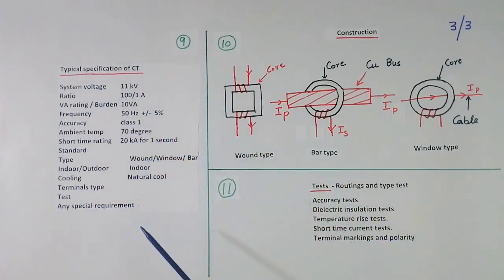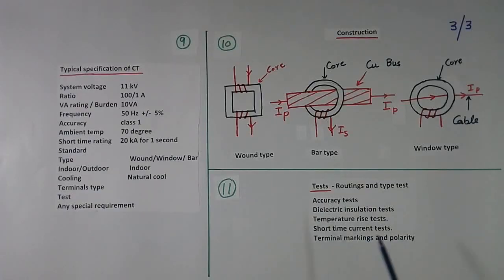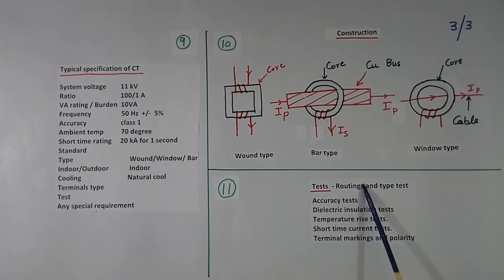Here I have shown this much. But in industry, specification will run in many pages. Now we come to test. Routine and type. Suppose we buy 100 CT. Then routine test are those which are done in all 100 CT. And type test are those which are done only in 1 or 2 CT.